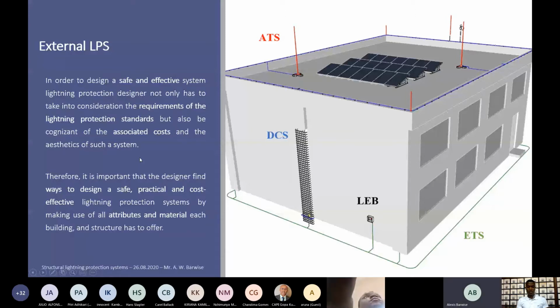I state here that in order to design a safe and effective system, a lightning protection designer not only has to take into consideration the requirements of the standards, we know that, but also has to be cognizant of the associated costs. It means nothing to build a massive, over-the-top system, such that the costs are high but it is not effective for the protection itself.